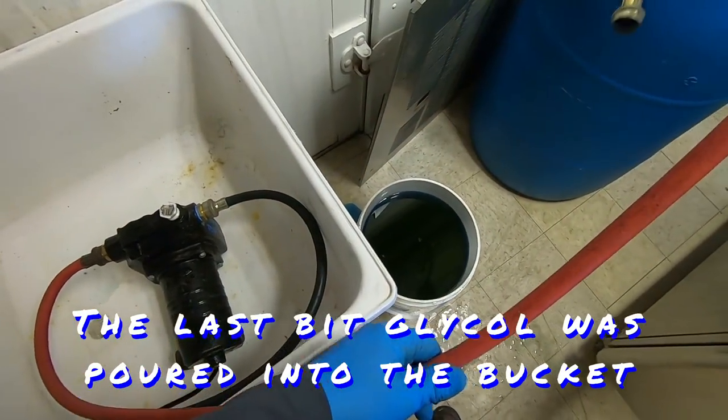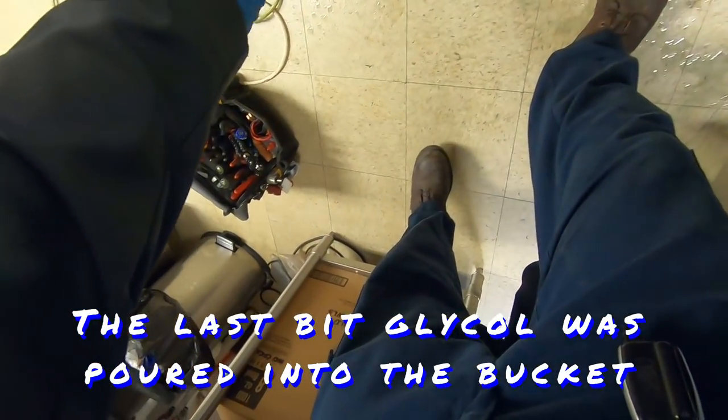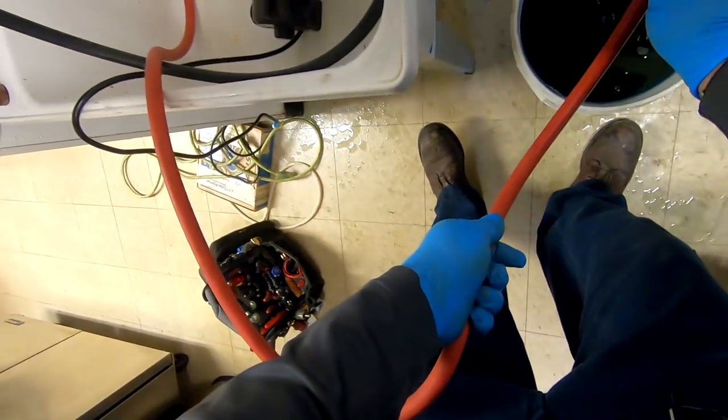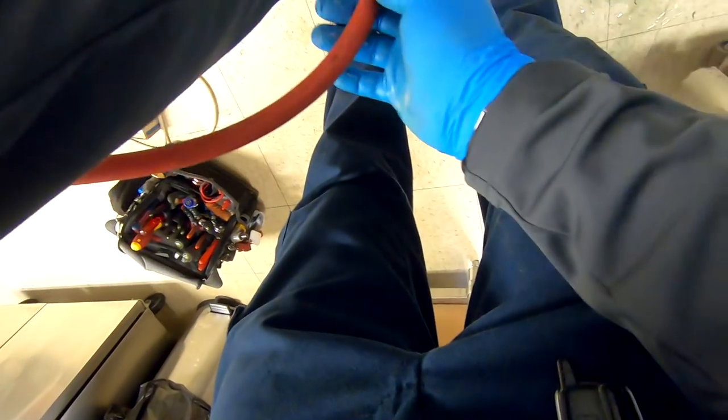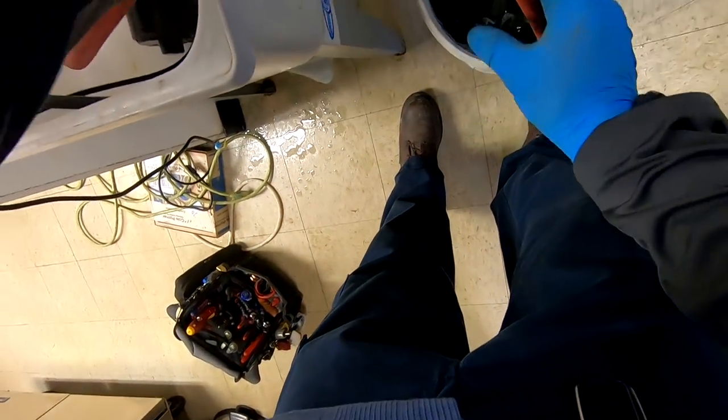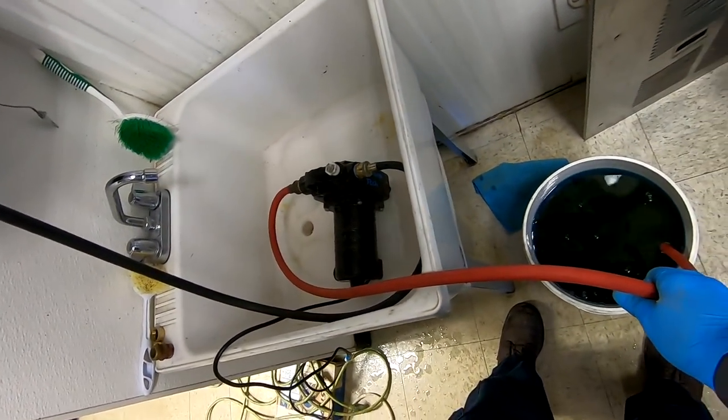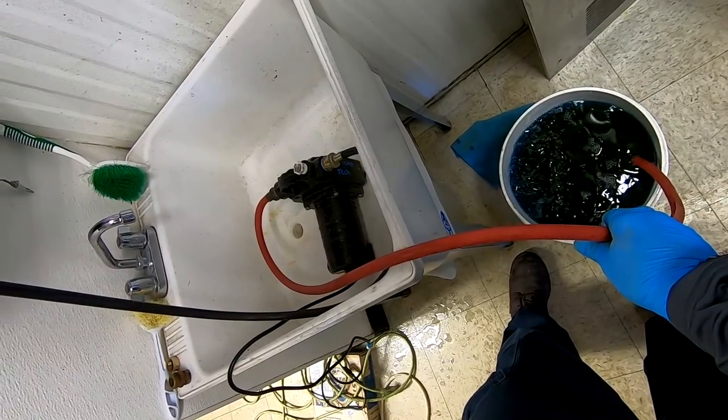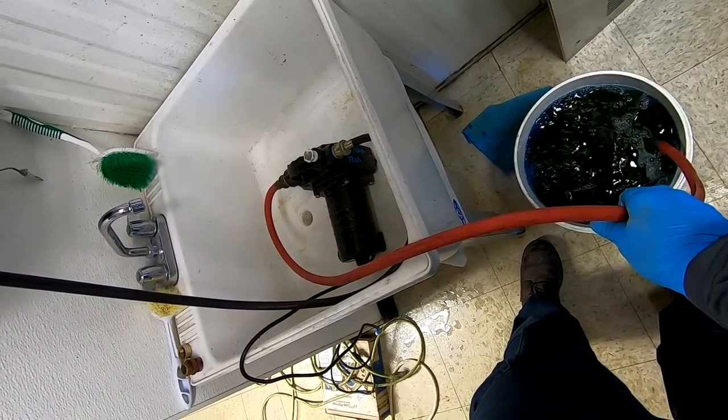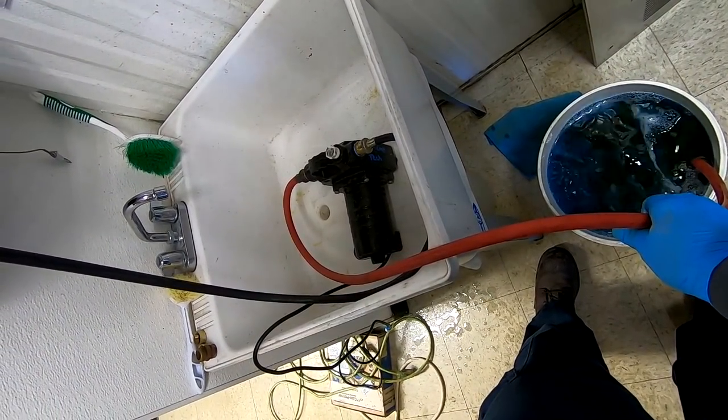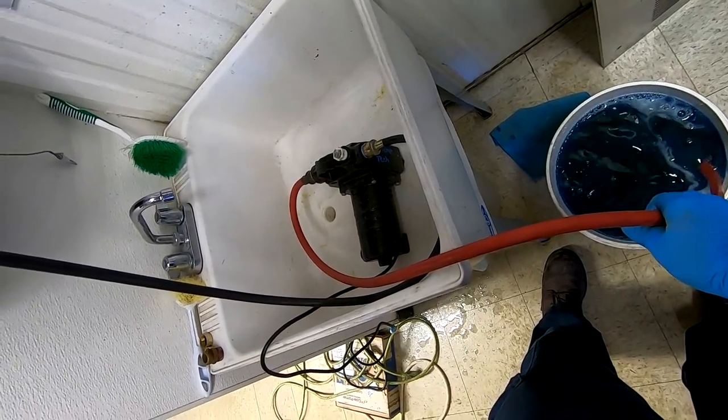These pumps do not prime worth a crap, so what we'll do, we'll let this drain backwards through the pump here and that'll prime itself. Watch the bubbles - there's some bubbles. No more bubbles, so now we're solid. Now we can plug it back in, it'll suck it right up.